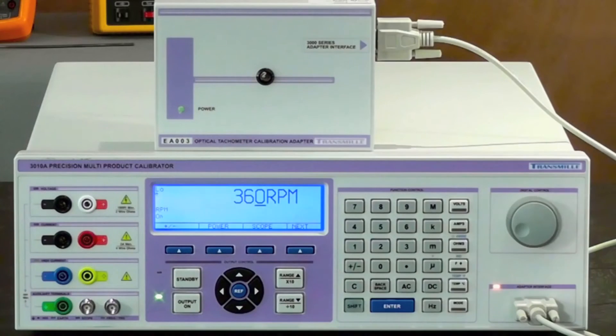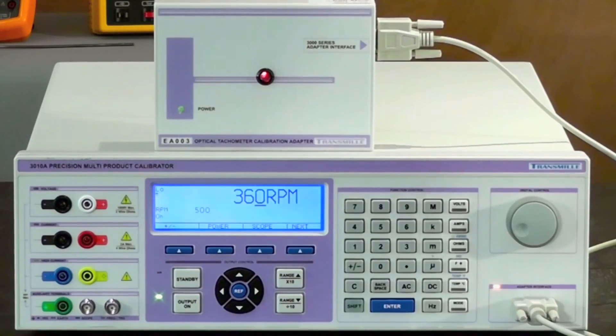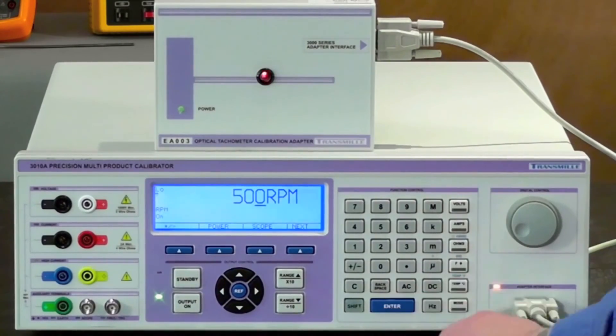To set the RPM of the adapter, use the numeric keys to enter a value between 60 and 60,000, for example 500, followed by pressing the blue enter key to confirm.